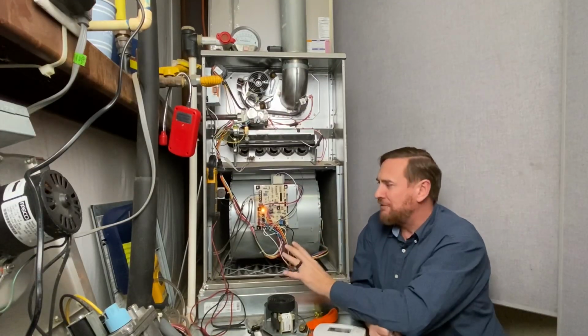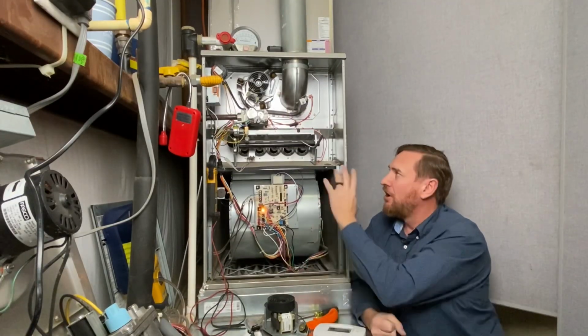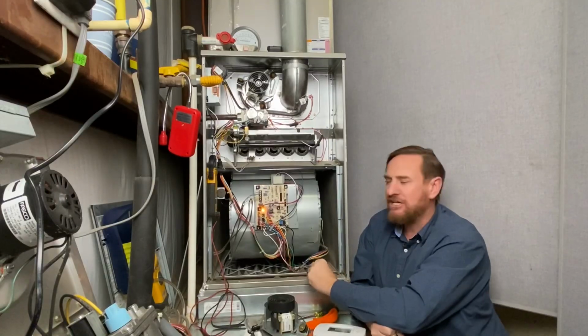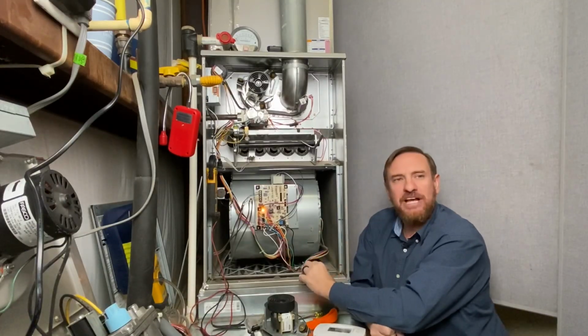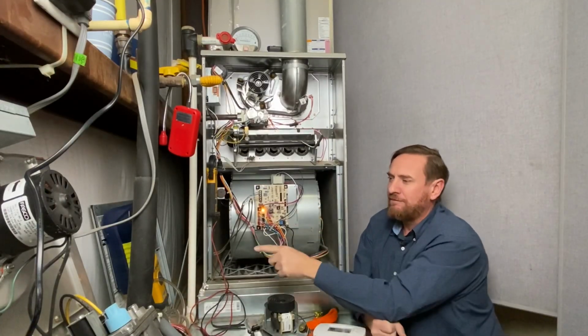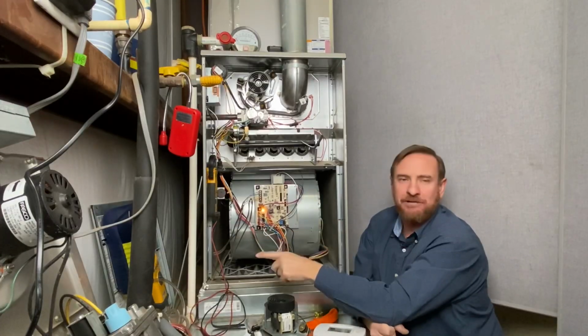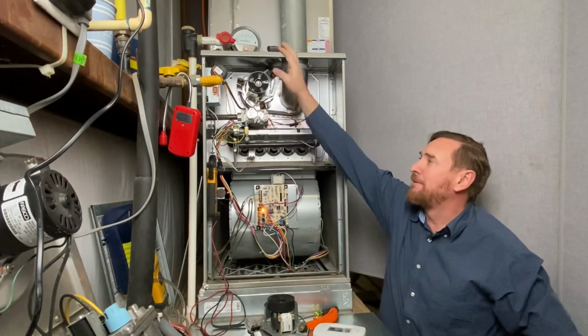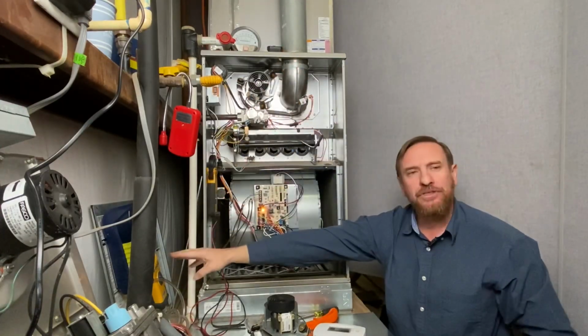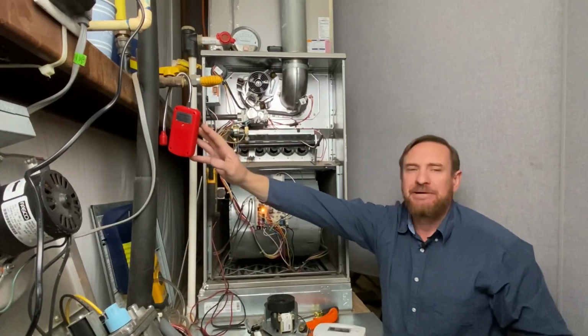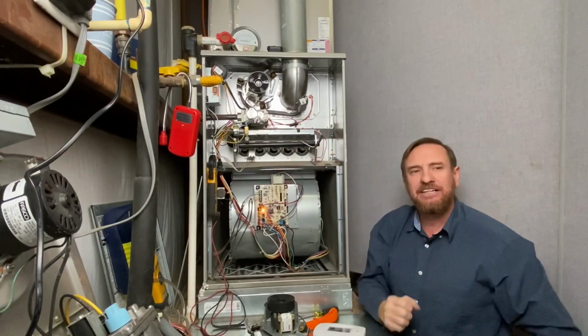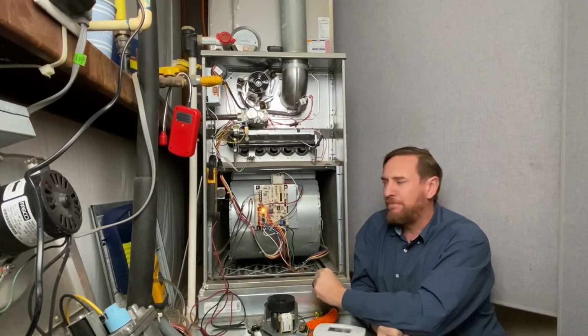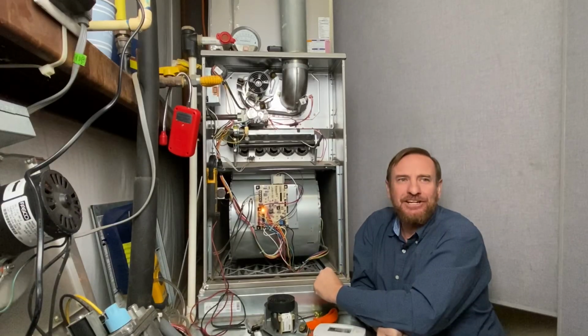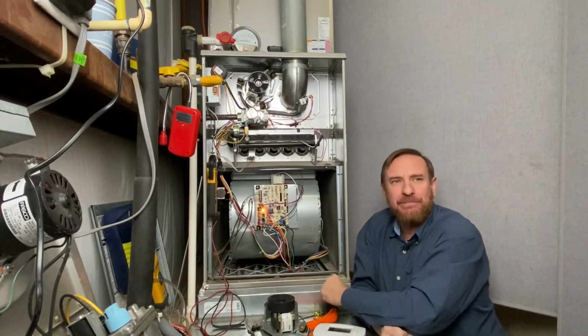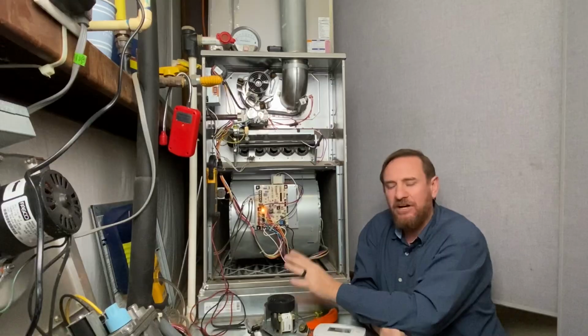There is much, much, much more that goes into this gas furnace. All these safety components that we need to be checking, and that the control board checks, we're going to talk about those. We're going to talk about combustion analysis. We're going to talk about checking for carbon monoxide. I have my personal CO monitor with me, the carbon monoxide monitor, and also my gas leak detector to see if there's any gas leaking. We're going to go and break down all these components, but that is our basic and fairly short sequence of operation of an 80% gas furnace with a hot surface igniter.